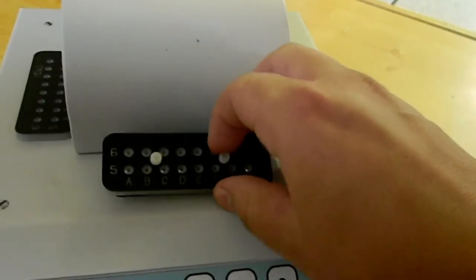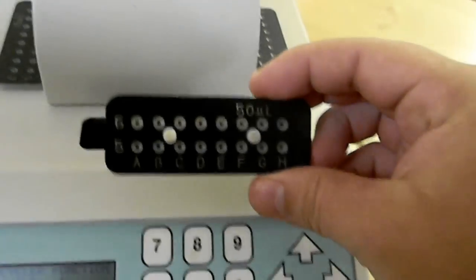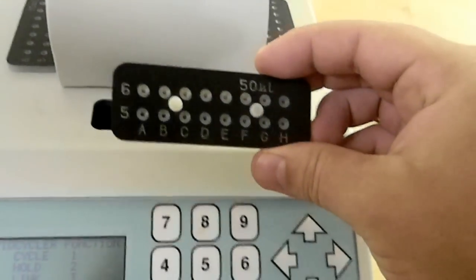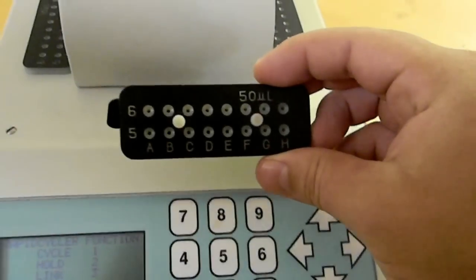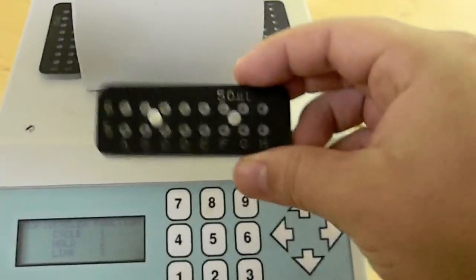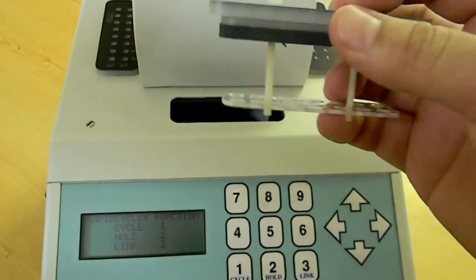Now another difference between this and conventional PCR machines is that it doesn't use those plastic tubes. It actually uses glass capillary tubes. This one's set up for 50 microliters, this deck set up for 10 microliters, and this deck is also set up for 10 microliters. But neither of these have this little stand that goes down the bottom.